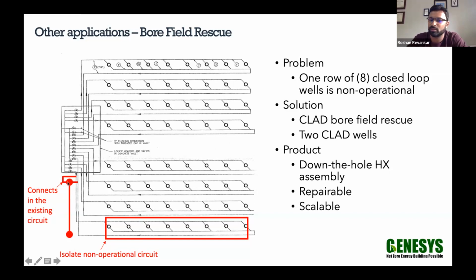So this is going to be the production well. This is going to be the discharge well. The production well just connects right into the circuit that was non-operational and discontinued. So the rest of the system stays the same with balancing of flow. The entire system is now going to be up and running with less than 90-degree entering water temperature on the heat pump side. So essentially, you can think of this as down-the-hole assembly, repairable, scalable, if there is groundwater available, which in this case there is.